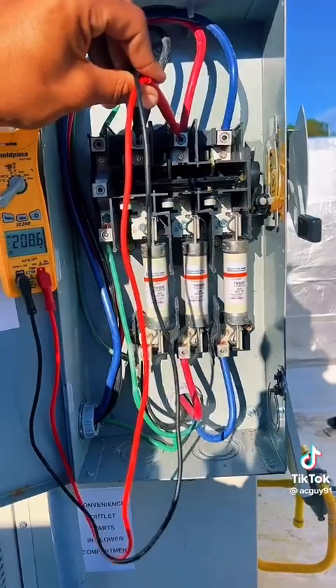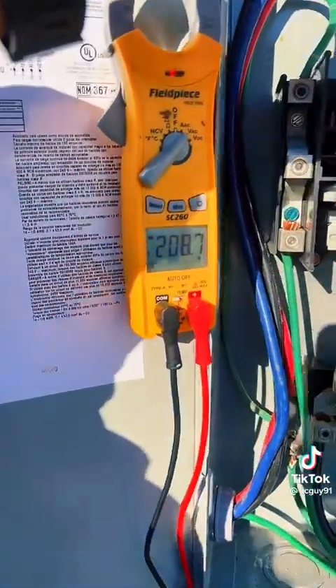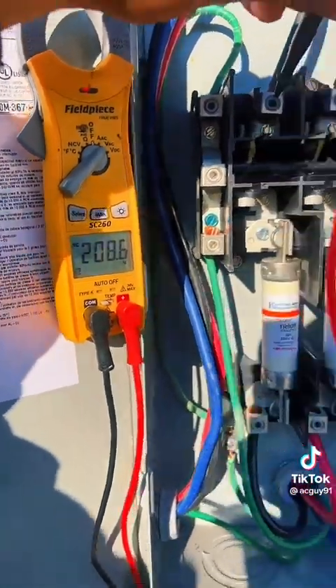Let's do it. So remember guys, we always want to keep this troubleshooting process simple. We're going to start with the basics. We got no power at the stat. Sure, I could go to the float switch. I can go to all the things that cut control voltage out to the unit, but I'm gonna start from the basics. I'm gonna go straight to the disconnect and let's make sure our breaker's on. I mean, that's step number one, right? So there's my disconnect. I have verified that I do have 208 volts coming in, so I know I have power going to my transformer.